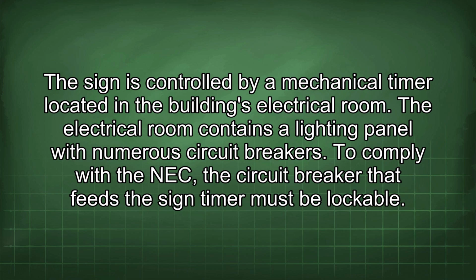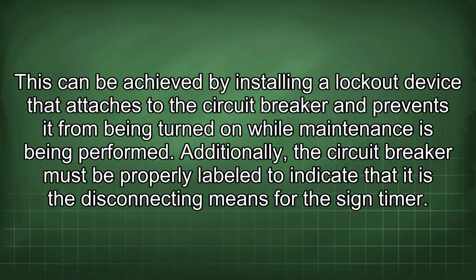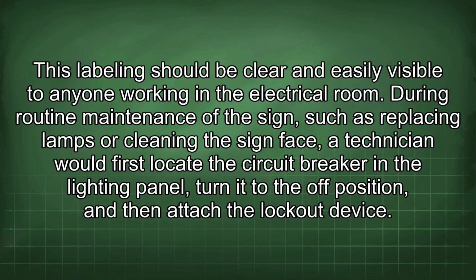To comply with the NEC, the circuit breaker that feeds the sign timer must be lockable. This can be achieved by installing a lockout device that attaches to the circuit breaker and prevents it from being turned on while maintenance is being performed. Additionally, the circuit breaker must be properly labeled to indicate that it is the disconnecting means for the sign timer. This labeling should be clear and easily visible to anyone working in the electrical room.